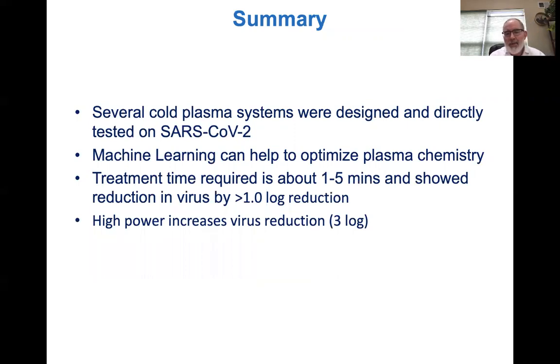And this is the summary. I outlined several cold plasma systems that were designed and directly tested on SARS-CoV-2. Machine learning was used to help optimize the chemistry of the device, and that was the guiding principle for us, to really improve the design and reduce complexity, and also make it as simple and user friendly as possible. The treatment time required is about 5 minutes if low power is used, or close to 10 to 30 seconds if a medium 10 kilovolt voltage is used. The high power jet, characterized by about 16 kilovolts of applied voltage, reduced the virus by 3 logs in about several minutes.